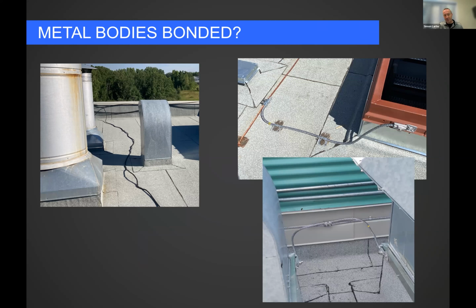That lower vent on the right-hand side there, that's a metal body of inductance because it's going to be in the zone of protection from those higher vents to the left there. But that wasn't bonded the way it should have been. And of course, on the right, you can see metal bodies that have been bonded in conformance to the code. So yeah, are they bonded at all? That's another thing to look for.